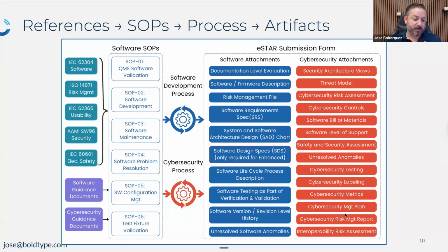Yeah, we found that in our case, we tend to include that in the cybersecurity management plan because SOPs tend to be for the whole company. And if you're doing multiple projects, they're incorporated into it. So what we'll have in the SOPs is, hey, you need to make sure that you've got a cybersecurity risk management plan or cybersecurity management plan, and that it includes these various elements. But the game plan, if an incident happens, is not in an SOP, it's in the plan because it's specific to this particular product. Right? It's going to be very nuanced depending on the components and the architecture and the risk level of that specific product, et cetera. So what we put in the SOPs is here's what you'll want to include, and what you're going to do is more in the plan itself.